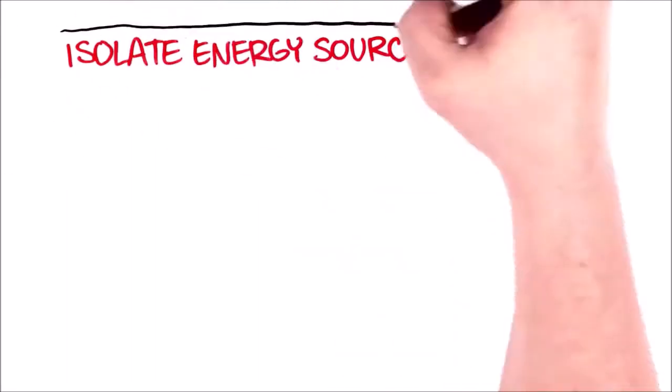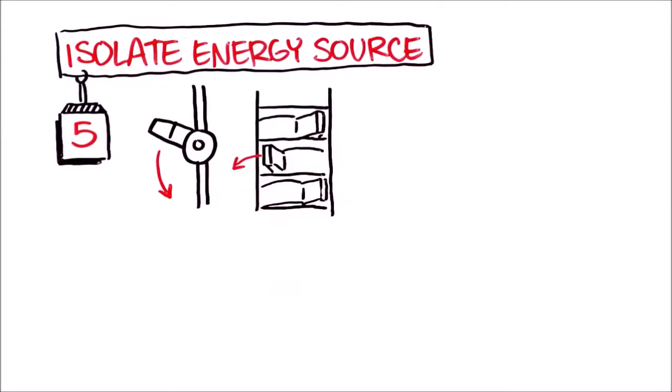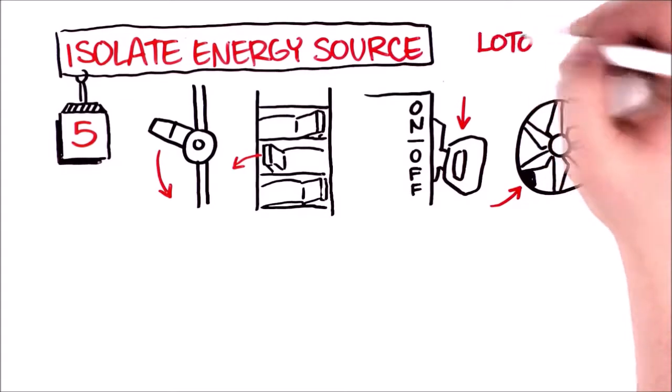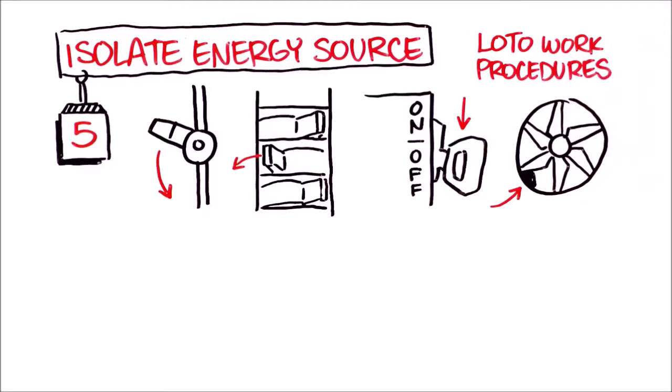You also need to isolate energy sources: turn off valves, flip circuit breakers, throw a disconnect switch, block a fan or hatch. When you're figuring out how to isolate the energy source, make sure you reference and follow the LOTO work procedure or instructions for the details.